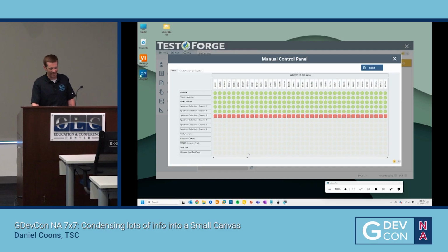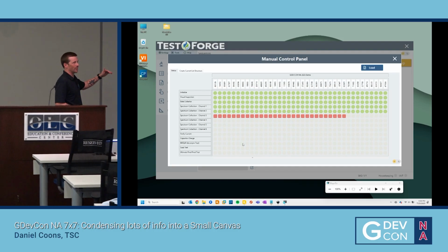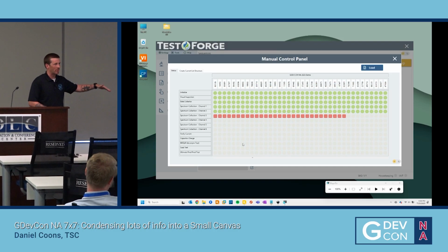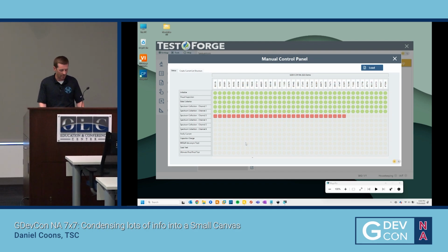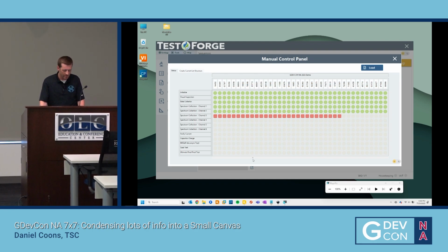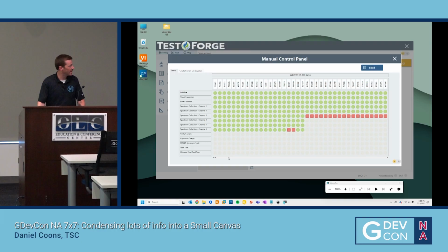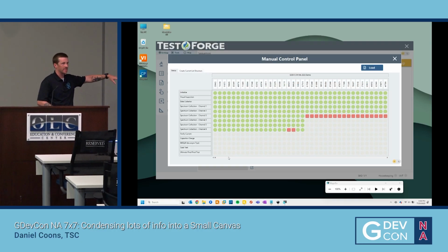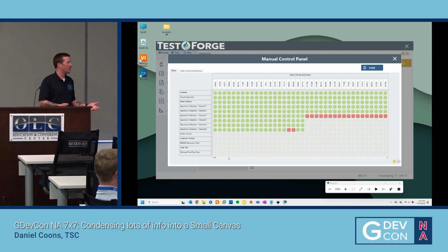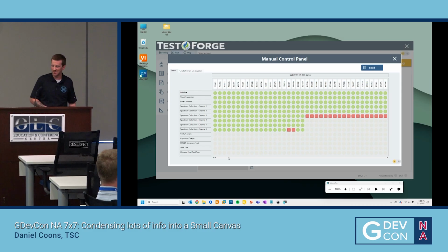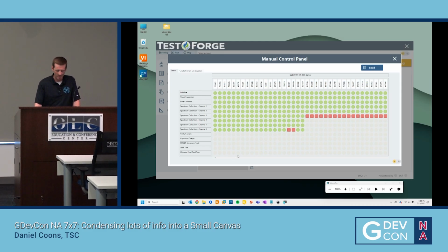Those red ones there, a lot of reds in a row, a lot of failures, maybe that's an equipment problem. They should go adjust the equipment, see if something's going on there, and then maybe retry some of these things. Versus something else, where we had a couple of failures and then some passes. That may indicate actual failed devices. So they all lead to investigation. If anything comes up failed, it's a major, major big deal, so they've got to know what to do with that.